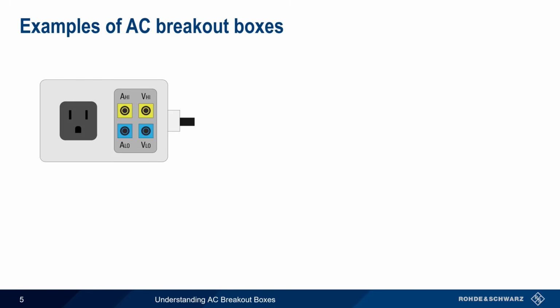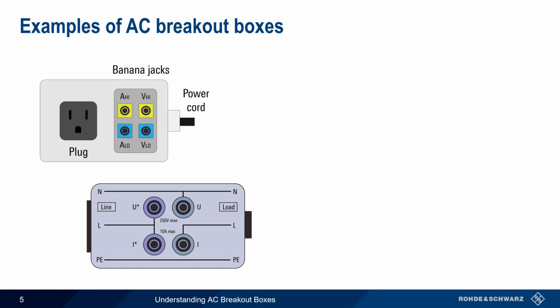Most often, an AC breakout box has a power cord for connecting to AC mains, and a plug or outlet for connecting to the device under test. As mentioned a few moments ago, voltage and current connections are made using standard banana-style plugs. Some variants use standard power cords for making the AC connection to both mains and to the device under test. Note that some AC breakout boxes have a wiring diagram on them, in addition to the labeled jacks.